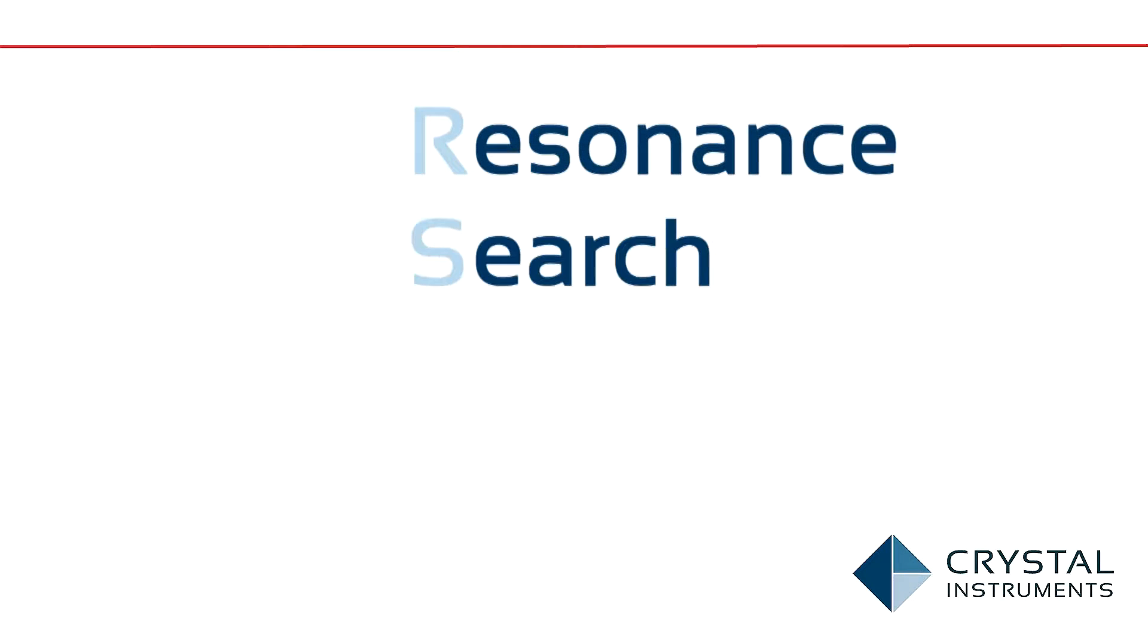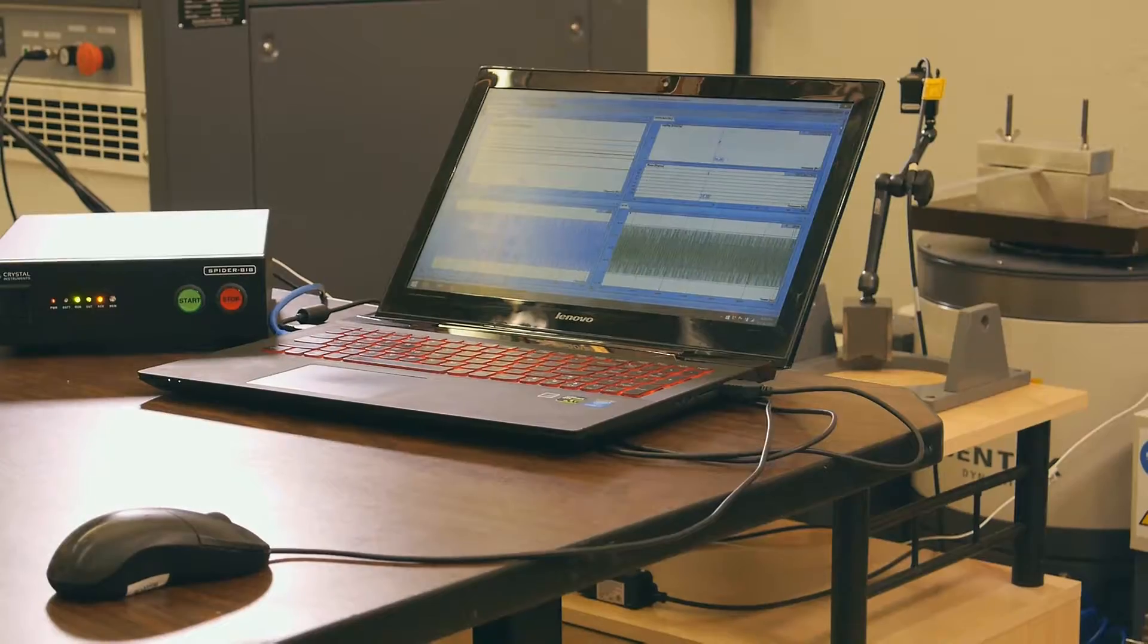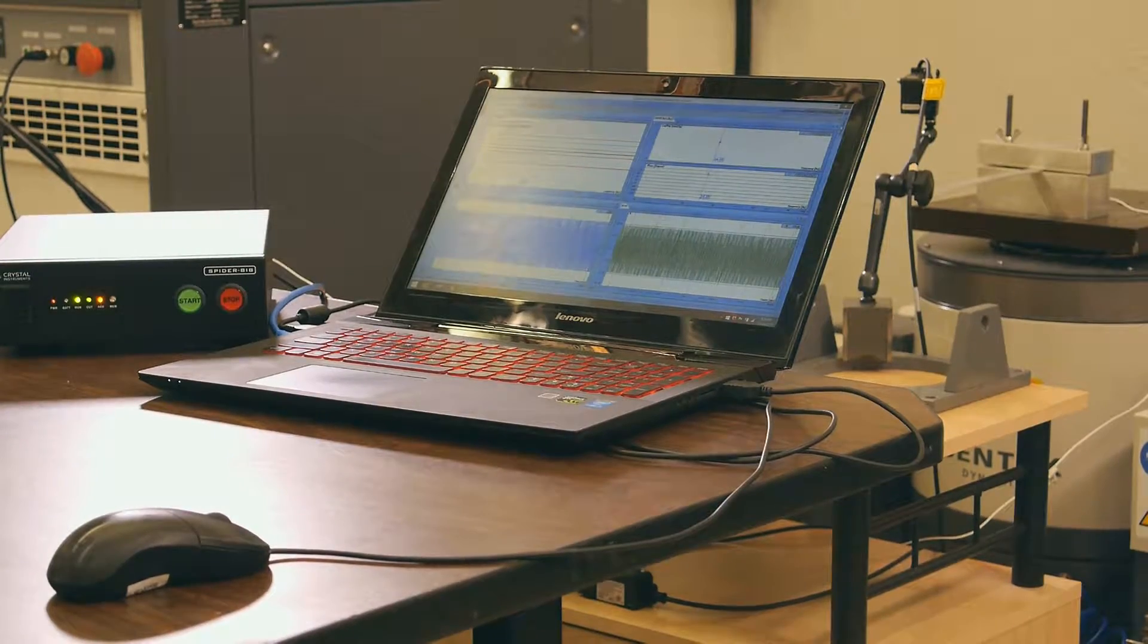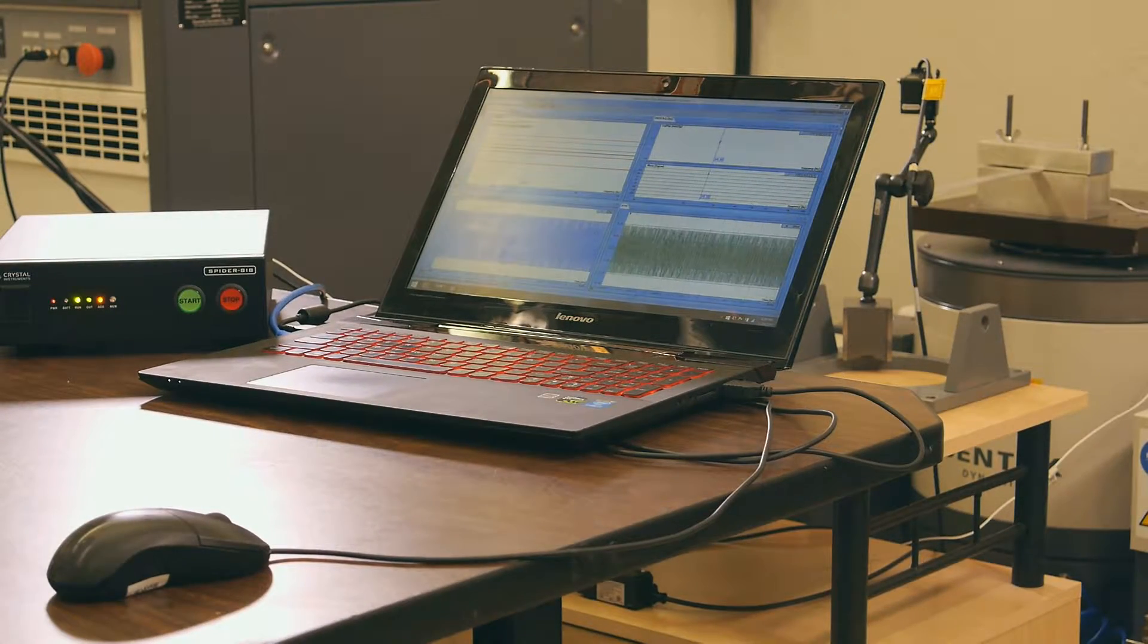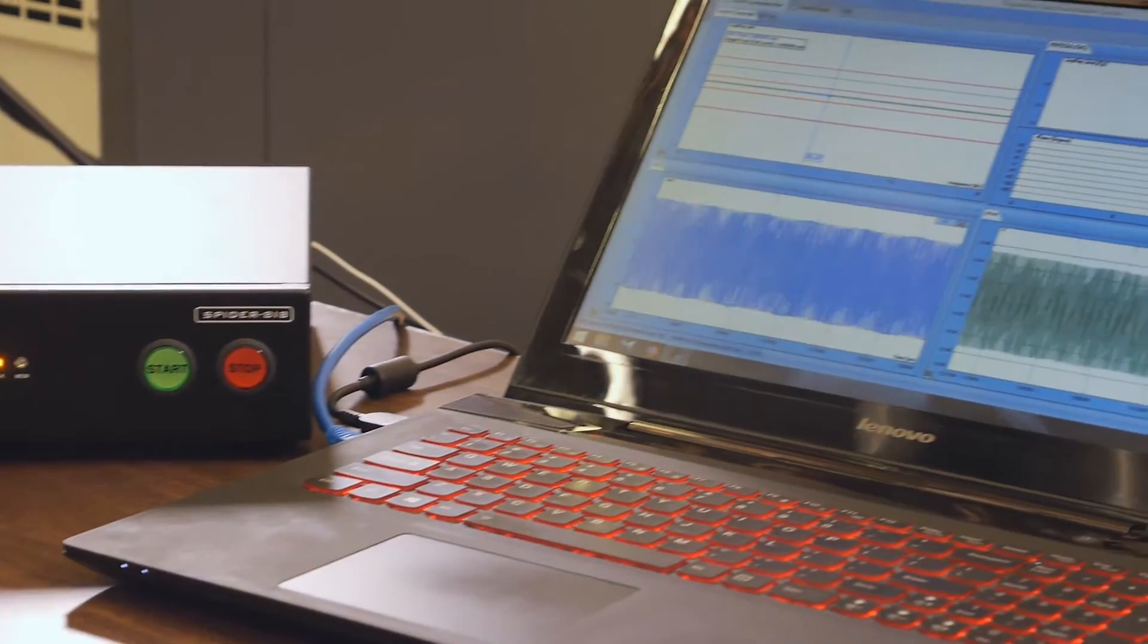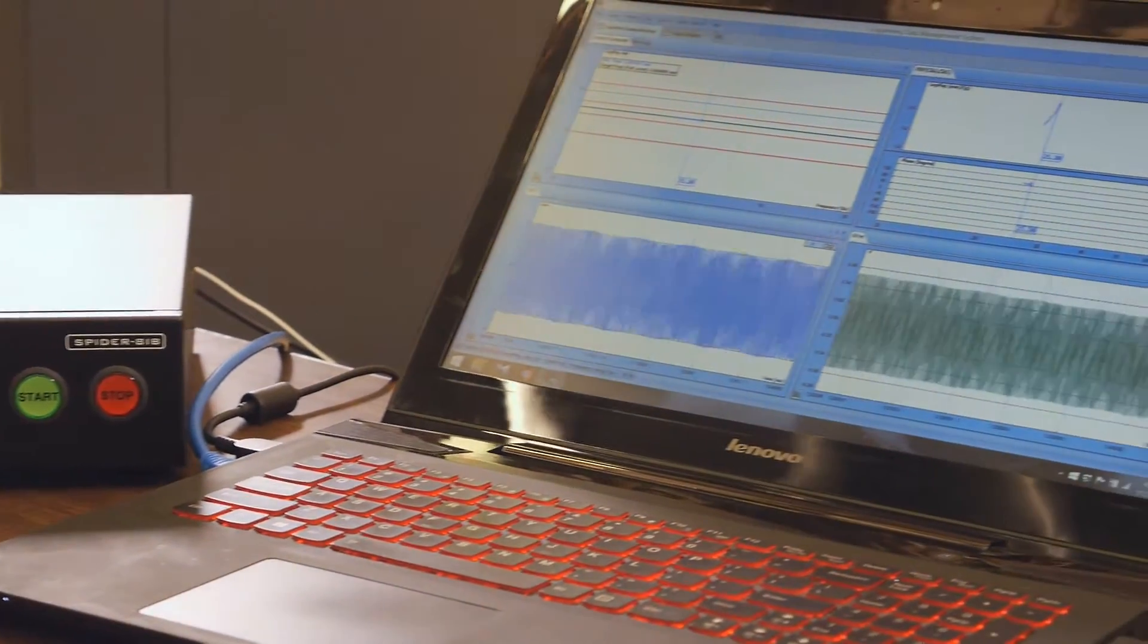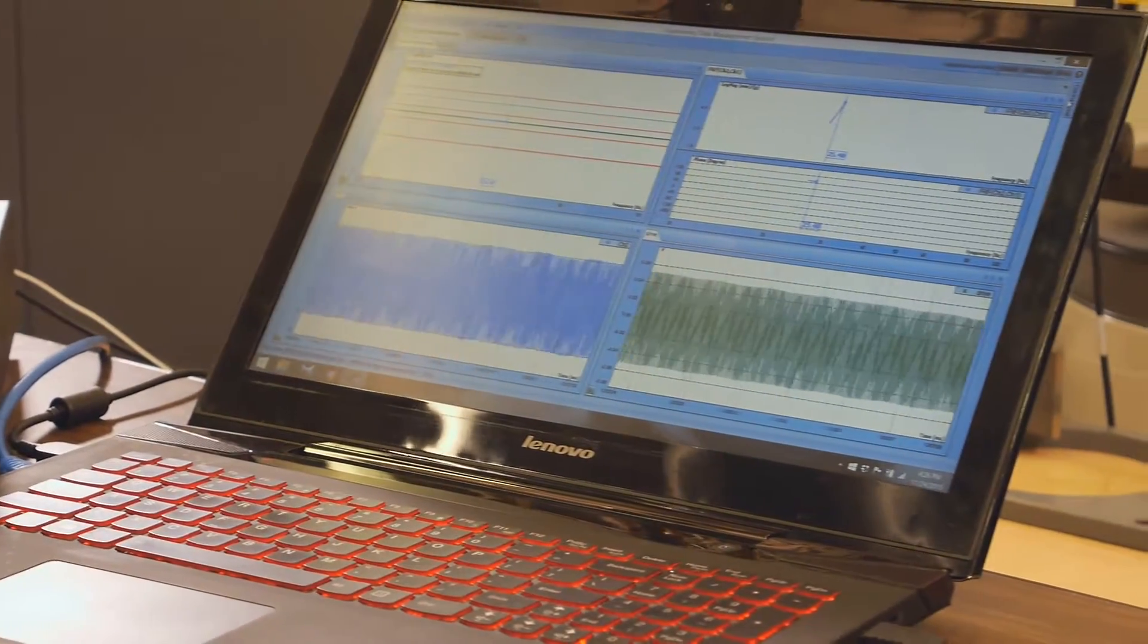One feature of sine tests is RSTD: Resonance Search, Track, and Dwell. This test, which is primarily used in fatigue and durability tests, can determine the resonance of a structure and then dwell at this frequency.